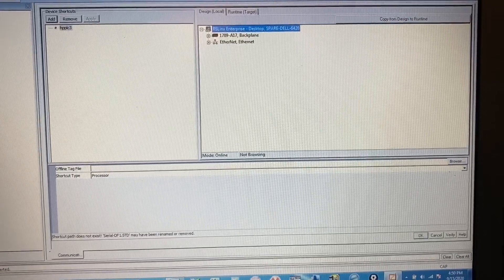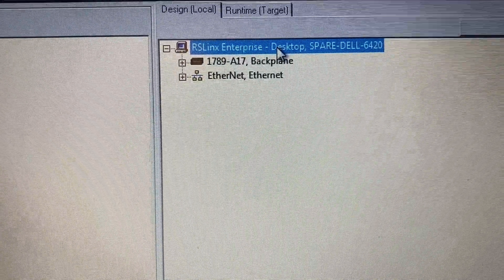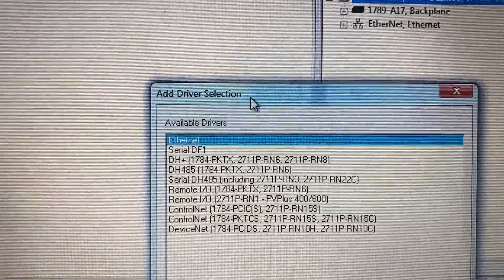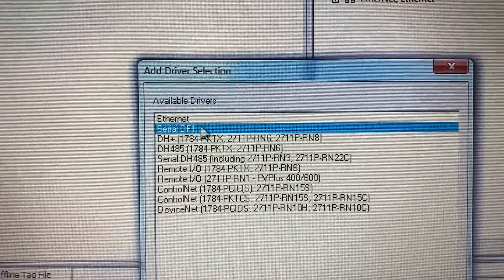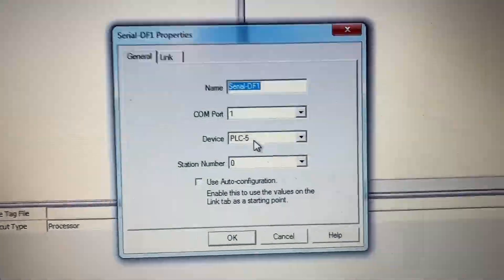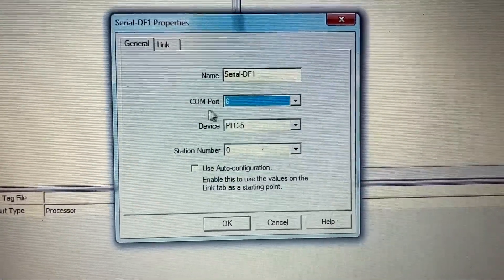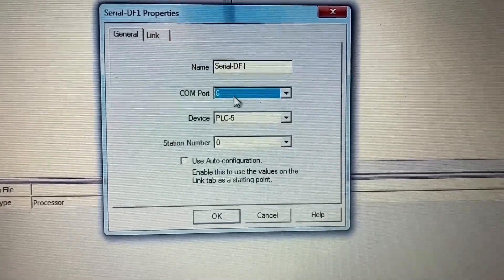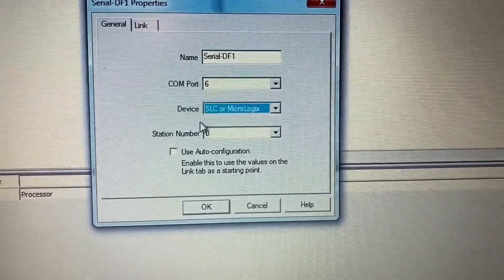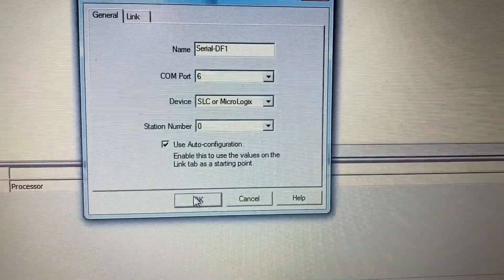In Communication Setup, under Design Local, right-click on RSLinx Enterprise and select Add Driver. Select Serial DF1 and click OK. Select COM6 for the COM port — COM6 is the port the PLC is connected to — then select SLC or MicroLogix for device and check Use Auto Configuration. Click OK.